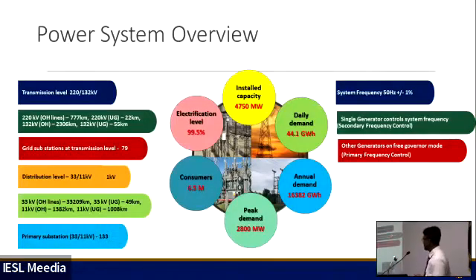In our system, usually a single generator controls the frequency, and that plant is responsible for maintaining the frequency at 50 Hertz. Apart from that, the other generators running on the system run in free governor mode; we can say they support the system frequency changes, they respond to the changes. That's how we operate the system to maintain stability. That has to be kept in mind when we're discussing total system failures. And we operate our transmission at 220 kV and 132 kV.